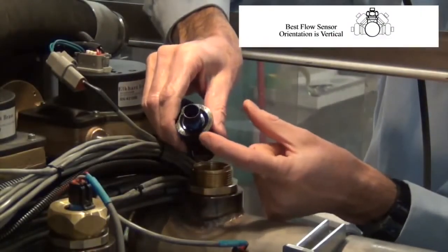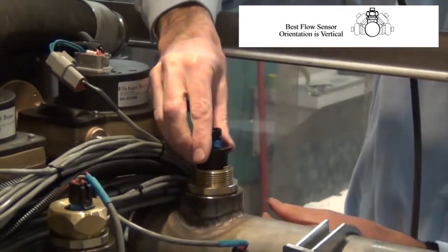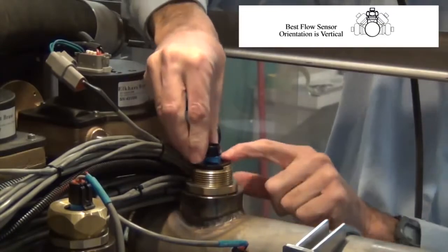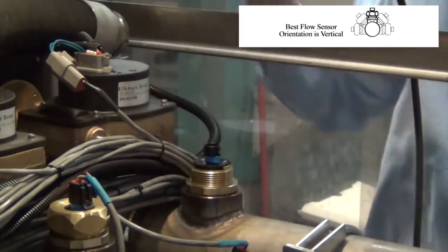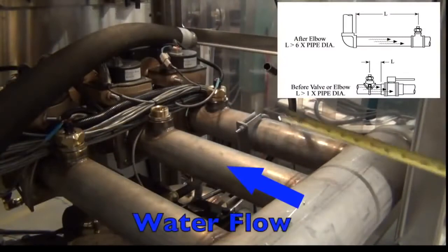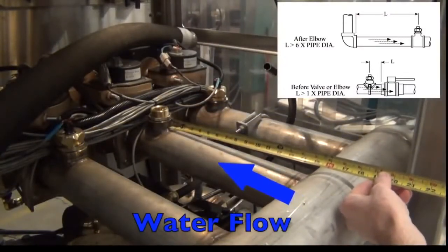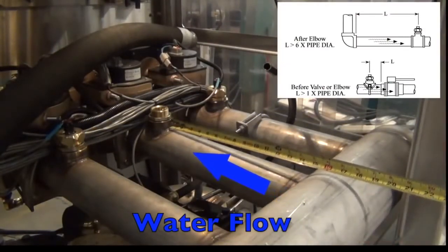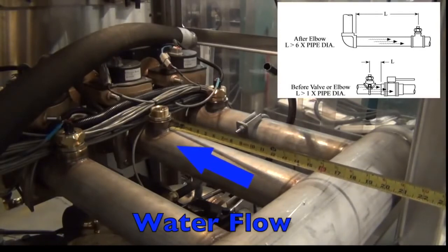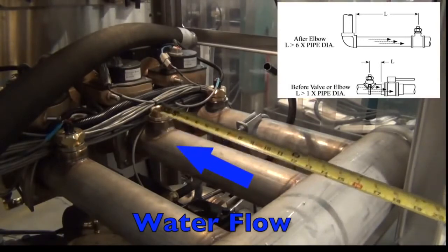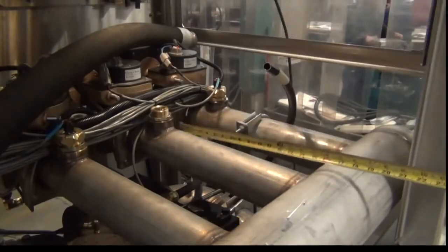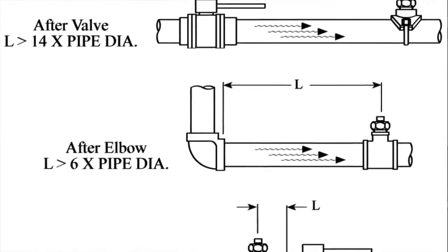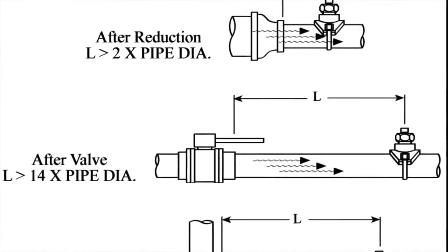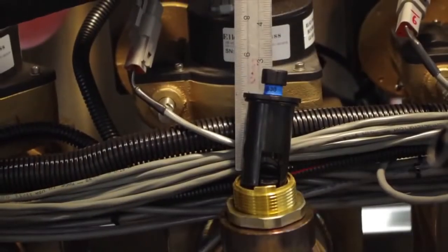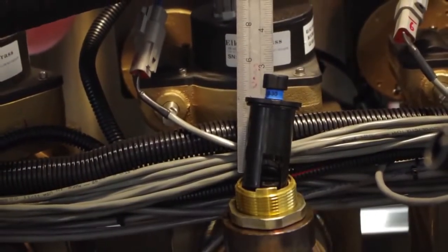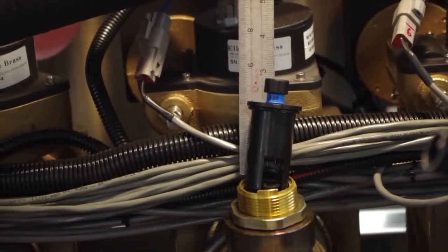The flow sensor should be mounted in an upright position. This helps prevent sediment in the plumbing from interfering with the paddle wheel. The paddle wheel flow sensor must be installed with at least 6 times the pipe's diameter of straight run pipe after an elbow. If that long of a straight run is not possible, use a stream straightener or contact Fire Research about other possibilities. Allow a minimum of a 3-inch clearance above the sensor installation.